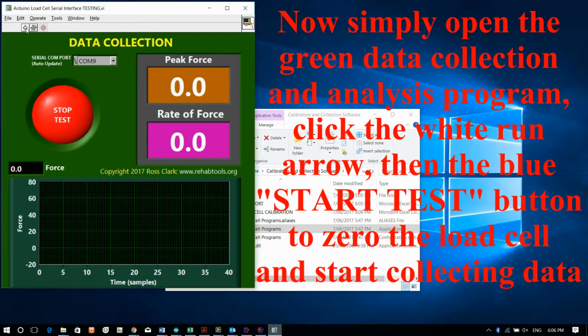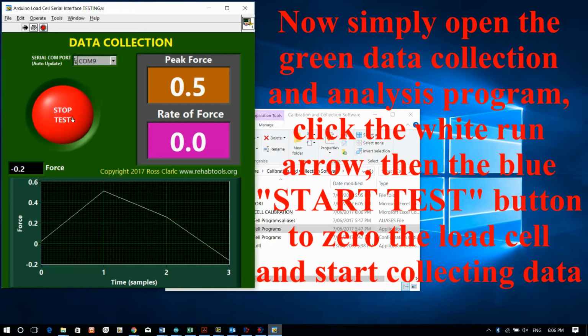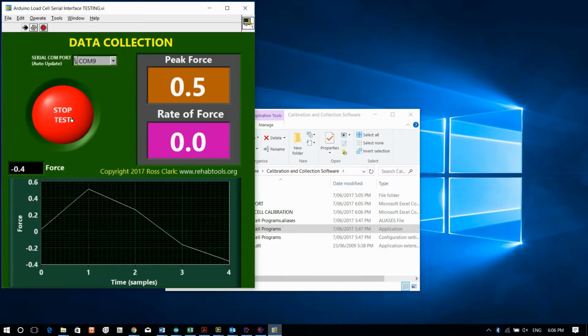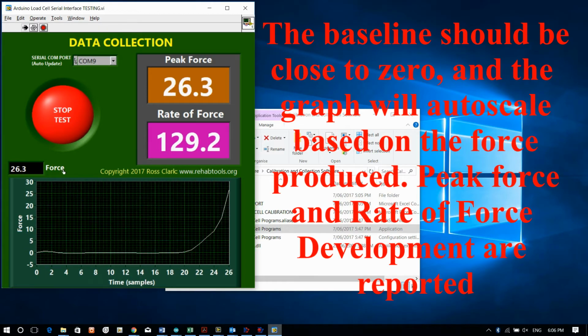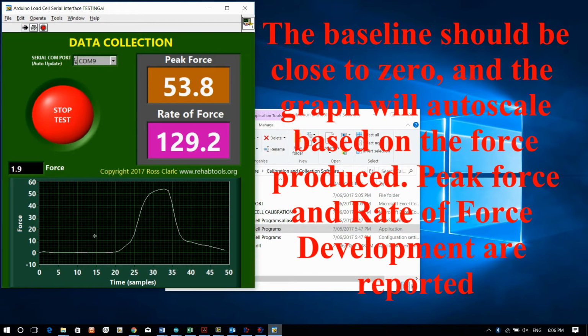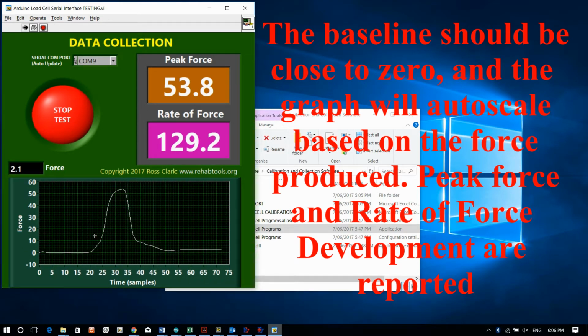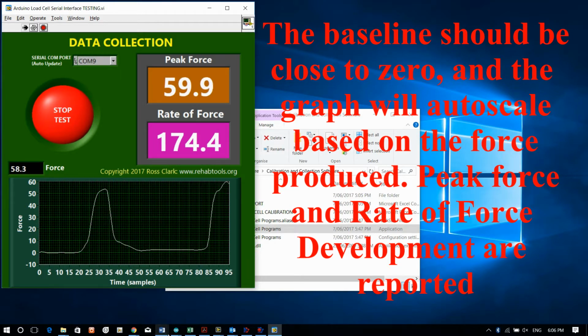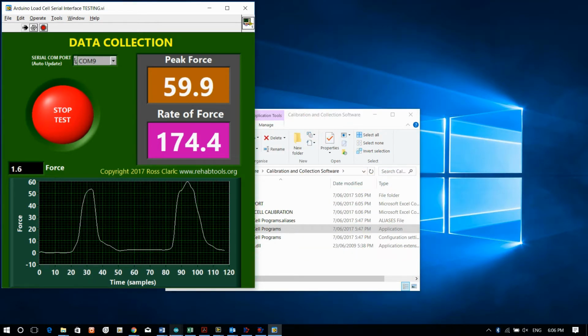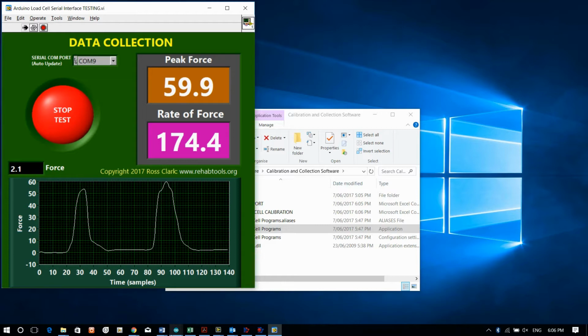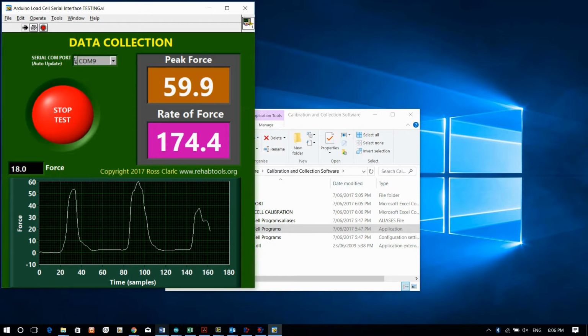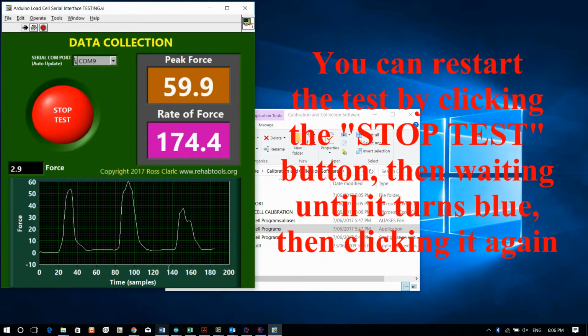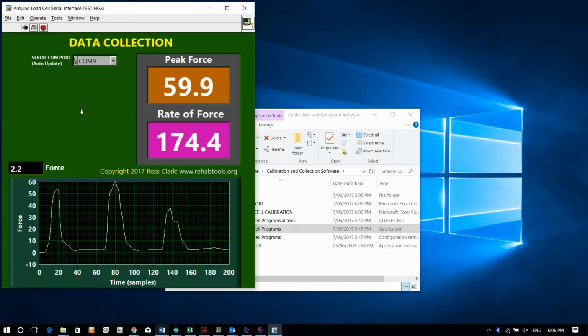Now we can open up the actual data collection program, click Run. It will automatically update the COM port to the one you selected in the calibration file. And then once you click Start Test, it'll start recording the data. What you'll see is the peak force and the rate of force development will change. It basically stores the last maximum for each value, so they don't necessarily have to be from the same trial. You could have a peak force in the second trial and a peak rate of force development in the third trial. When you finish, click Stop Test, and it will actually refresh itself.